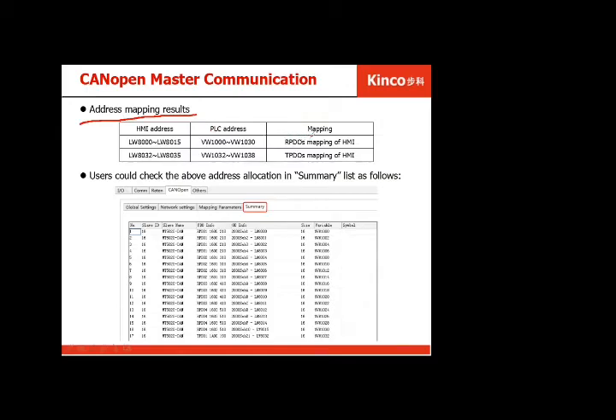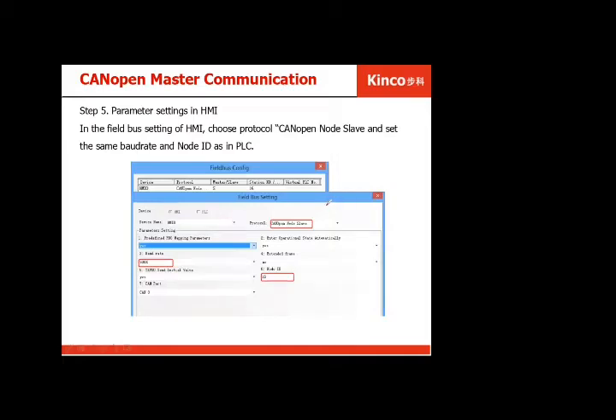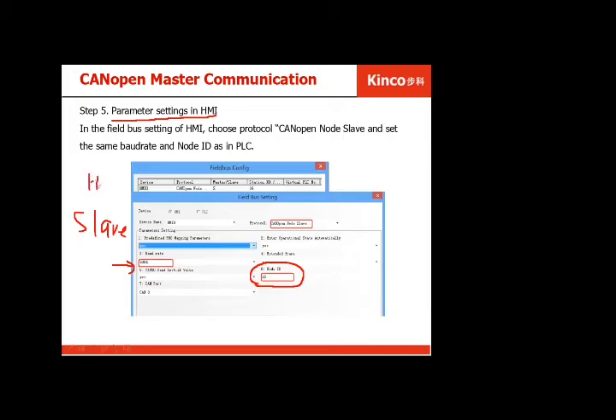The address mapping result shows the HMI address and PLC address from the RPDO and TPDO. You can also check this via the summary view. For the parameter settings on the HMI side, you need to set the same baud rate as the PLC, and also set the node ID — since the HMI is configured as a slave, the master can read or write to it using these settings.